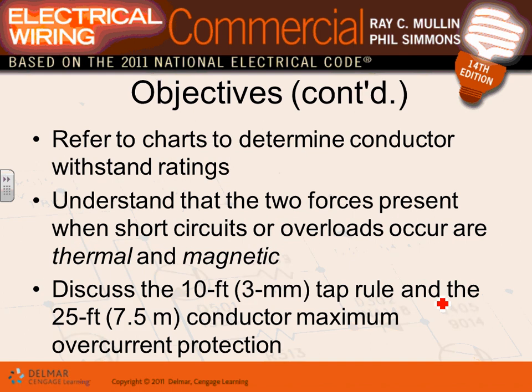There are charts that give you the withstand rating. You are the lucky ones that we use SKM. This is iChat, SKM PTW. When you pick a cable, every cable comes with a damage curve. What's a damage curve? It gives you the withstand rating of this cable. It tells you if you put this amount of current in this cable, it will last for this amount of seconds. If you increase the amps, it will last for a lower amount of time.